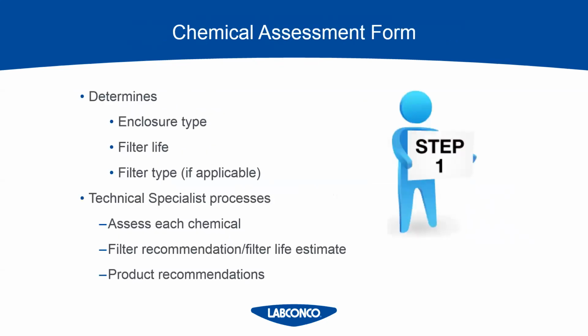No ductless fume hood can capture every chemical. So before you can consider one of these hoods, you have to fill out a chemical assessment form to make sure the application is compatible with the filtration. This is always step one in the process. This form is going to ask for things like the type of handling, chemical name, type of container, whether it's opened or closed, the dilution percentage, the temperature, handling frequency, quantity, duration of use, all sorts of fun things. When we're looking at the lifetime use of the hood, you have to take into account if an application is going to change. You would have to resubmit a chemical assessment form if the application does change, because the manufacturer will then be able to tell you if it's appropriate and how long the filters are going to last.